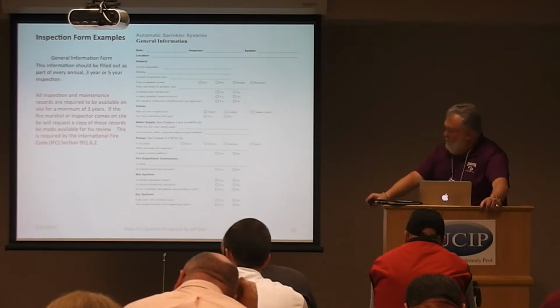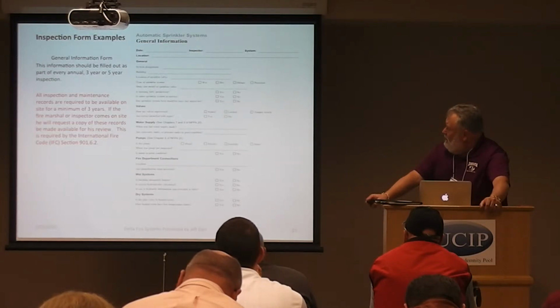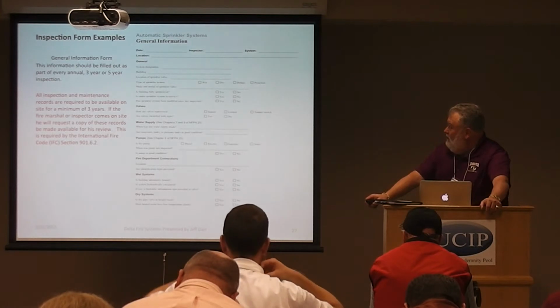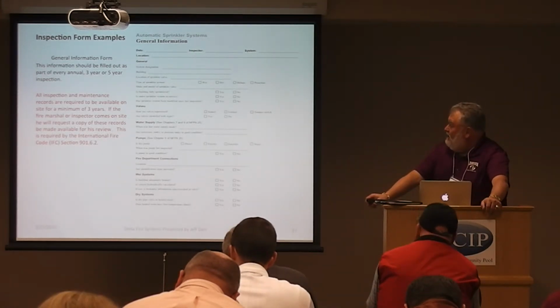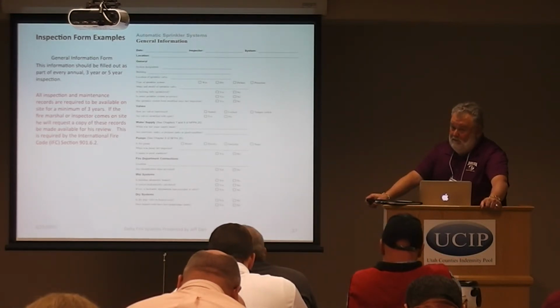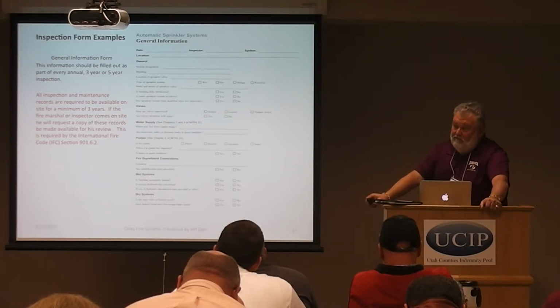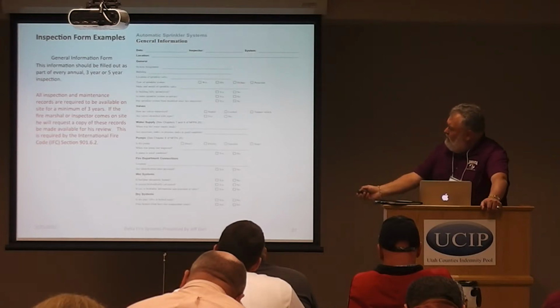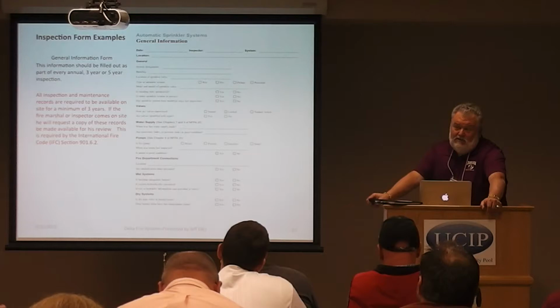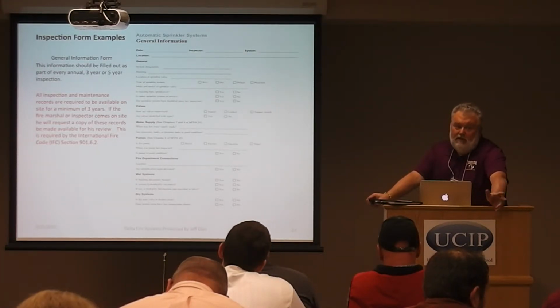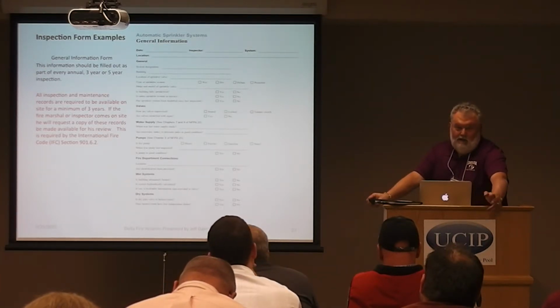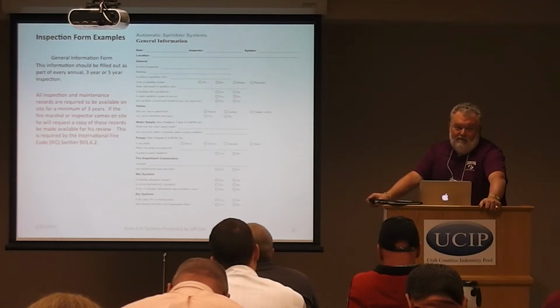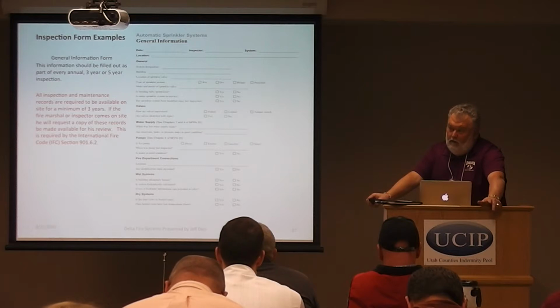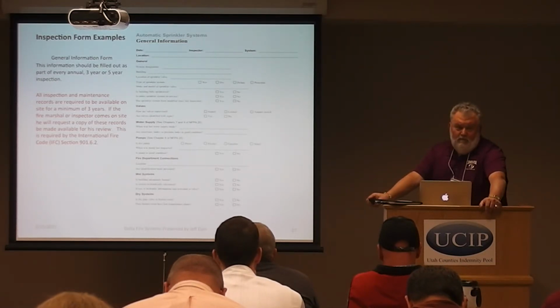Here's an example of the inspection forms. Like I say, you should have these for your use. By the International Fire Code, you are required as a building owner to have all inspection and maintenance records available on site for a minimum of 3 years. The fire marshal comes in, one of the first things he's going to ask is, let me see your maintenance records. As a company, we got away from leaving them on the site. We supply the owner PDF copies of everything and let them put them there on site, because paper copies have a tendency to walk away. The owners ask us more often than not to give them the PDFs for their records. That way they can have a copy on site. Oftentimes they have corporate headquarters where they also want a copy, so we're finding that works quite well.